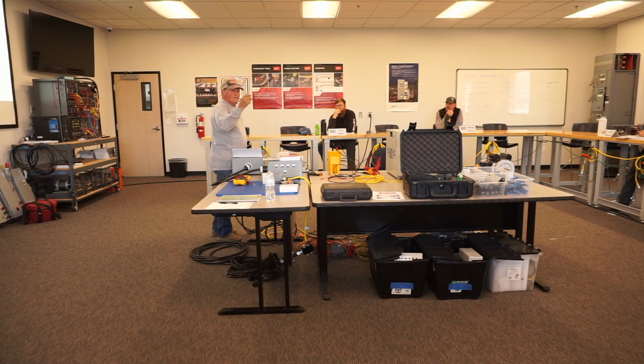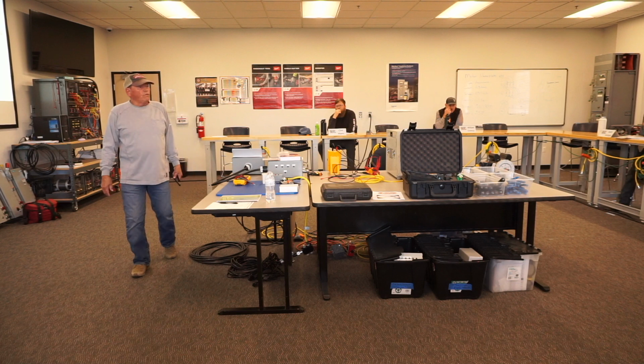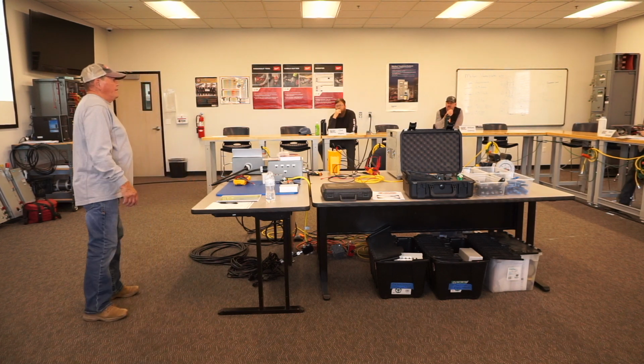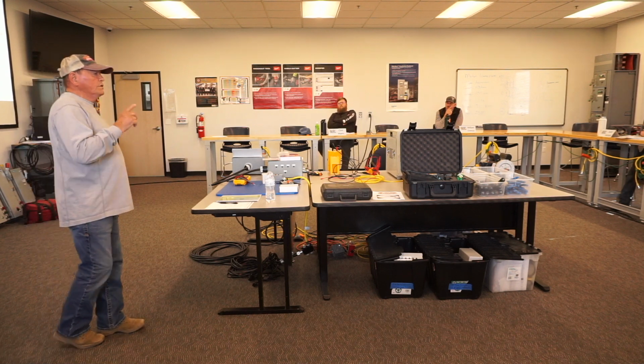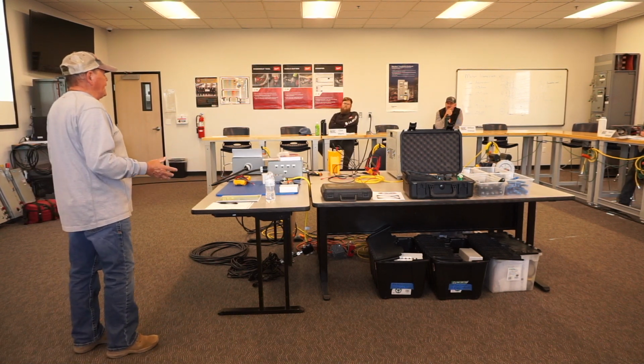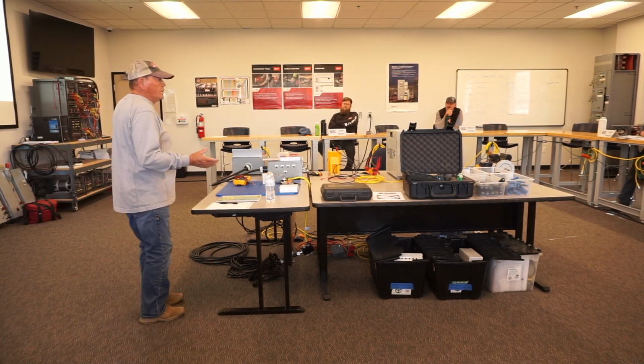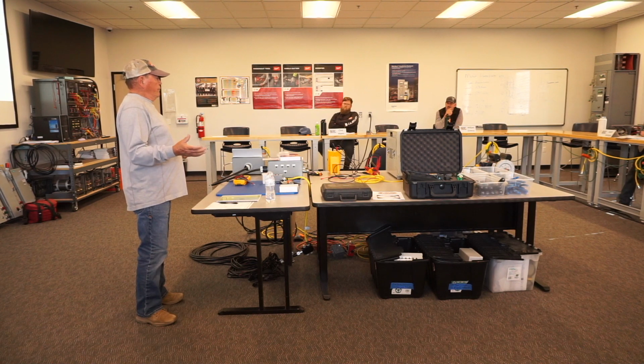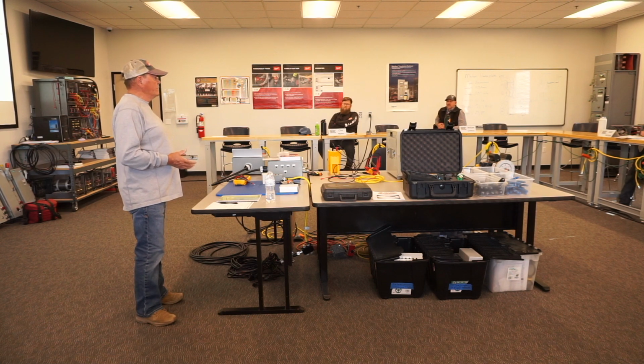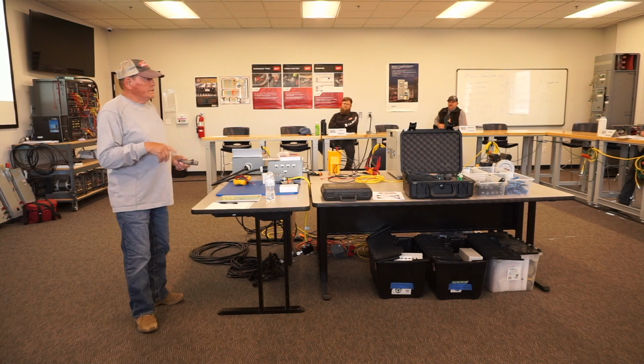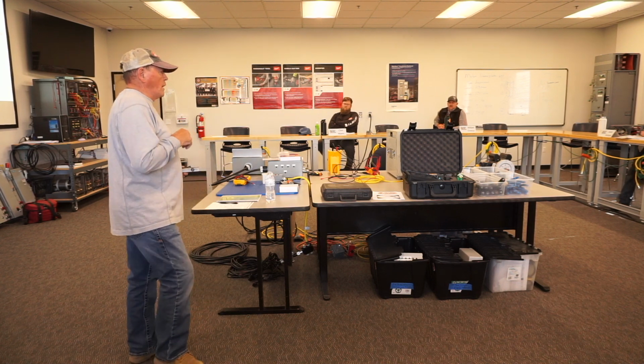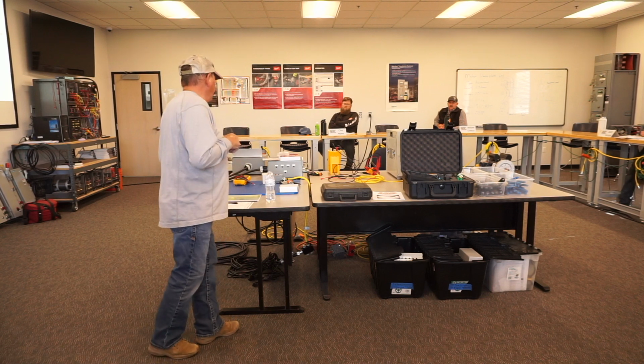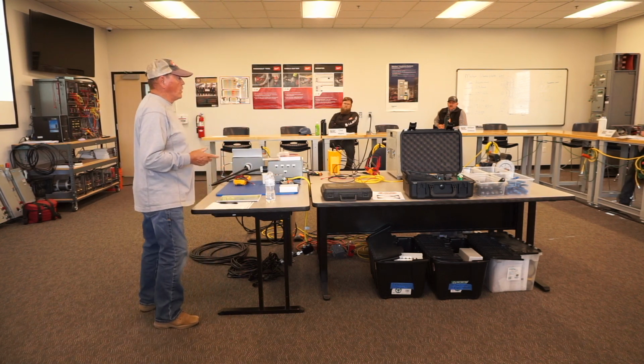These ferrite modules, which are pretty much here, eliminate the EMI, the high frequency that's on that cable. That 10,000 hertz signal generates EMI and RFI. Well, what's a capacitor? It's two conductors with an insulator. So my wire going to my motor is nothing but a gigantic capacitor, and that high frequency can couple through that wire and therefore causes EMI and RFI, depending on the frequency.